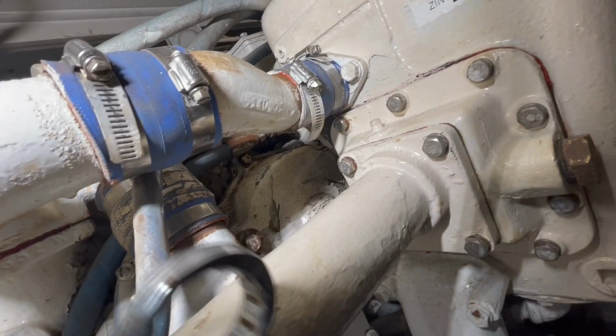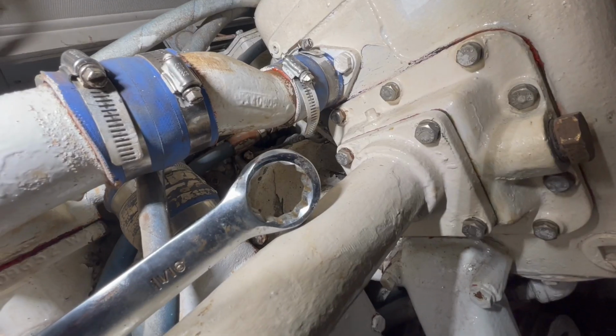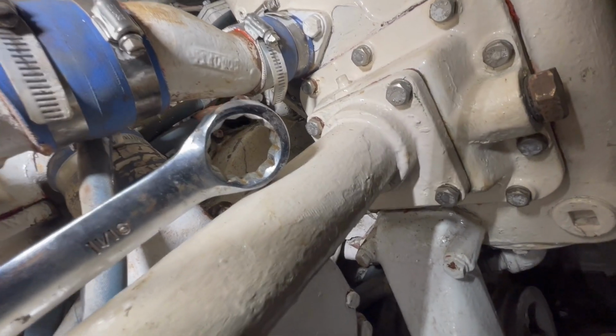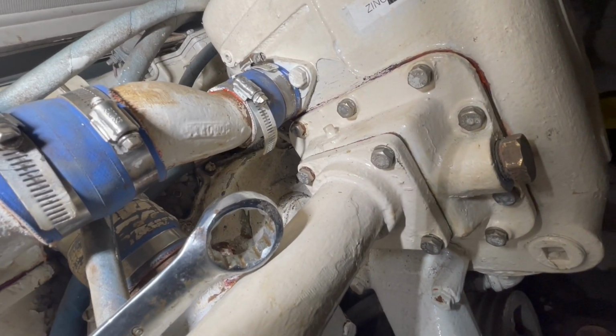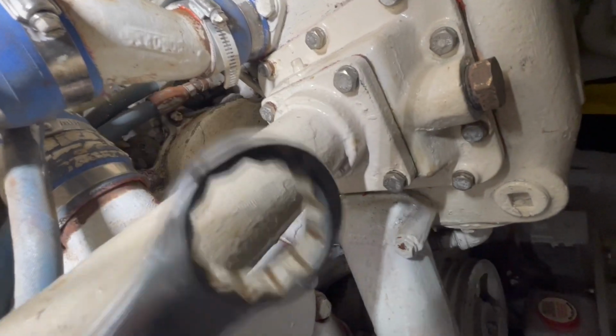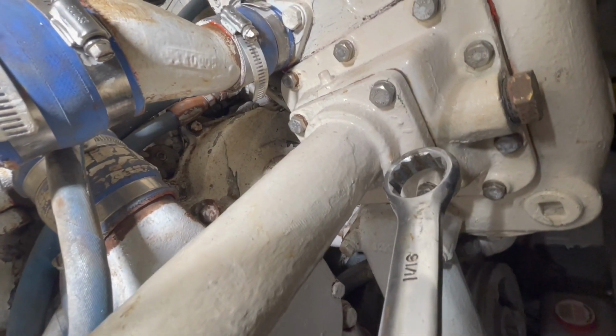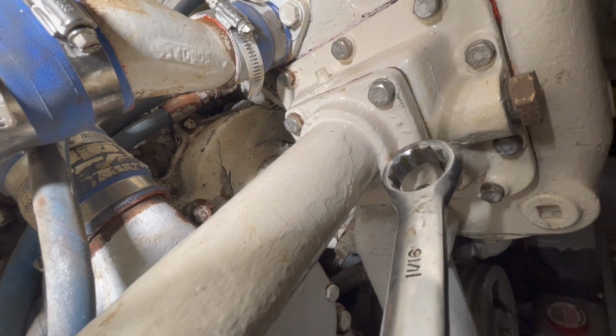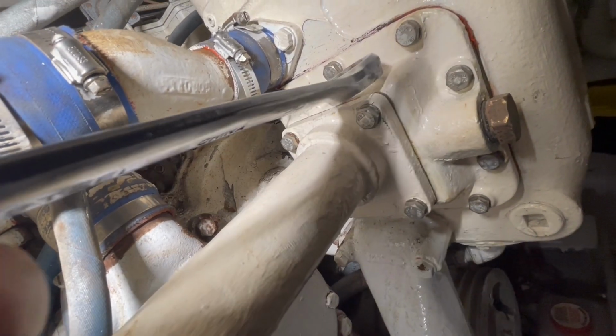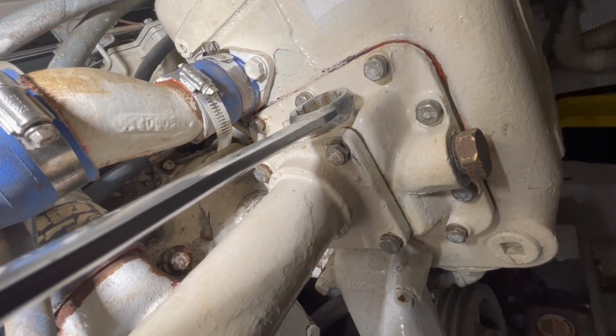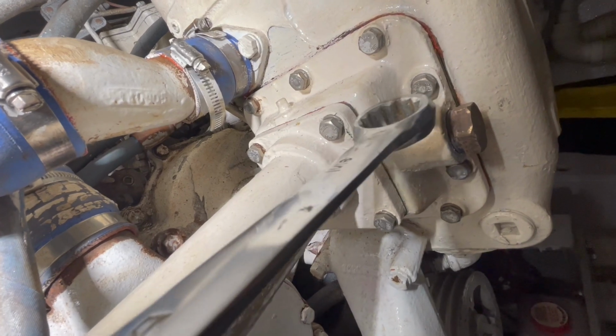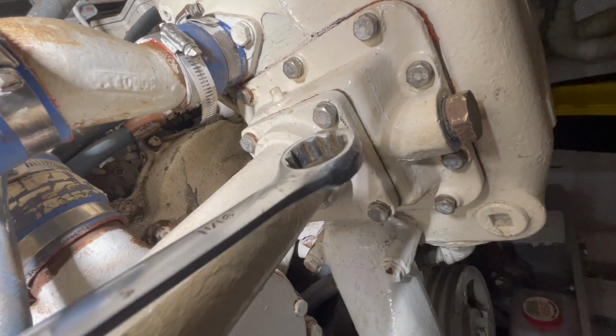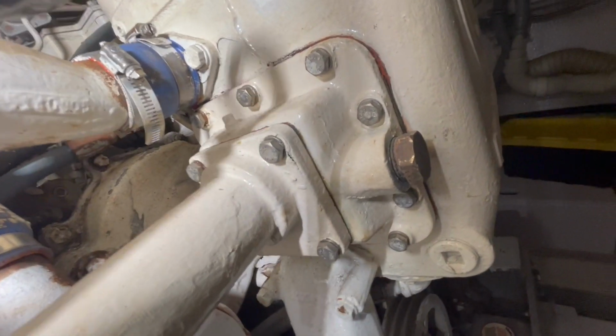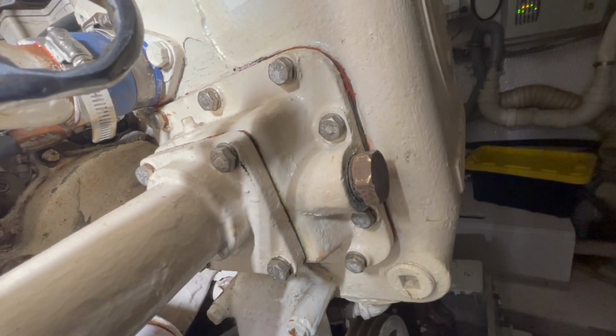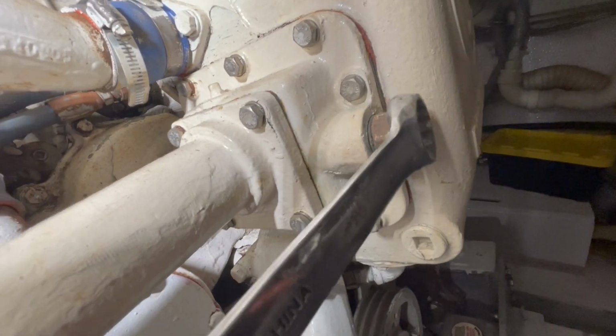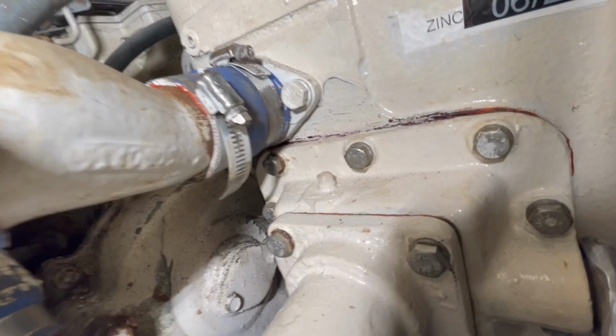This pipe is 1.5 inches in diameter where the solution comes out or in, and we've got a 3/4 inch bilge pump, so it's only going to pump to about right here before it flows out, but our heat exchanger goes up to here. So in order to get that up as high as we can, probably to the top of this pipe, we need to bleed the air out of the heat exchanger. So what I'm going to do, there's a little vent right there.